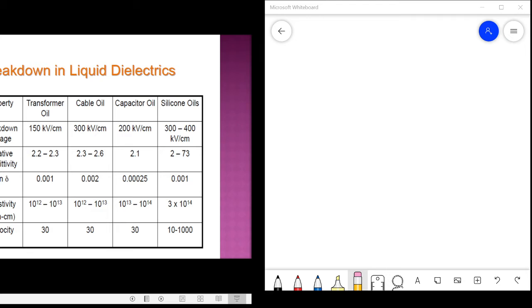Breakdown. Okay, so saya buat breakdown in liquid, tapi saya tengok bukan breakdown voltage, saya tengok partial discharge. Bila charge tu tinggi, capacitance effect tu tinggi dalam liquid tu, maksudnya insulator tu performance dia dah makin menurun. So ini tengok capacitor oil, silicon oil, paling tinggi, antara yang tinggi cable oil dengan silicon oil. Transformer oil, kalau pakai Hyrex ni, boleh sampai 150 kV. Cable oil boleh sampai 300 kV. Capacitor oil dalam capacitor, syarat kena tahan sampai 200 kV. Silicon oil 300 hingga 400.